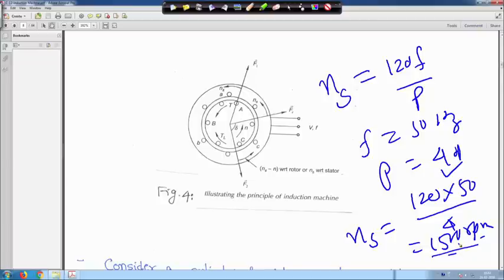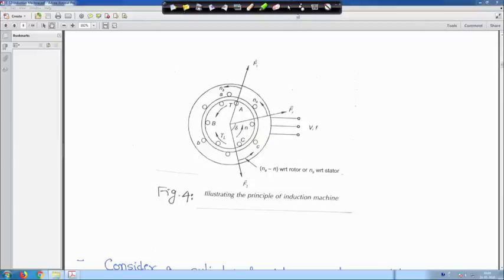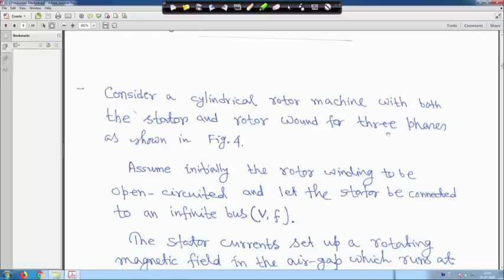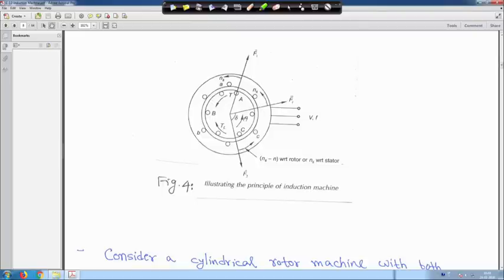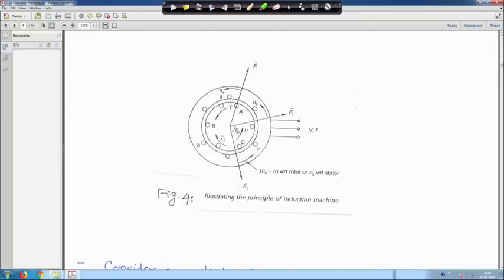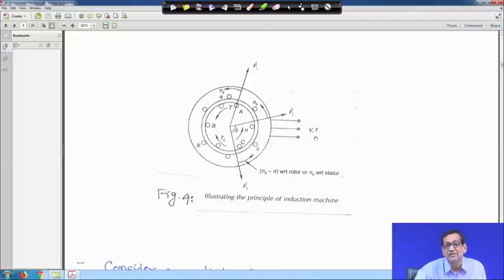Generally you will find it is a 4-pole machine. The three-phase magnetic field rotates at synchronous speed N_s — say 1500 RPM — and the rotor speed N will be less than N_s. Consider the cylindrical rotor machine with both stator and rotor wound for three phase. Assume initially the rotor winding to be open-circuited and let the stator be connected to an infinite bus — meaning the stator is connected to a supply where voltage and frequency are both constant.